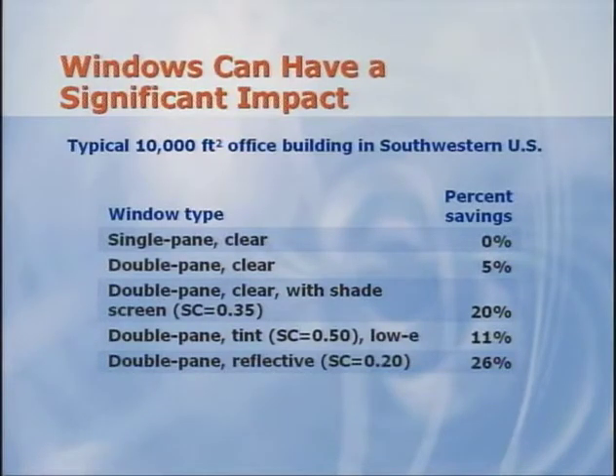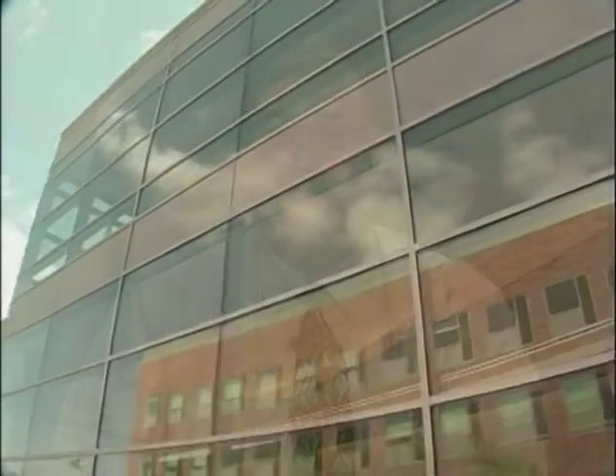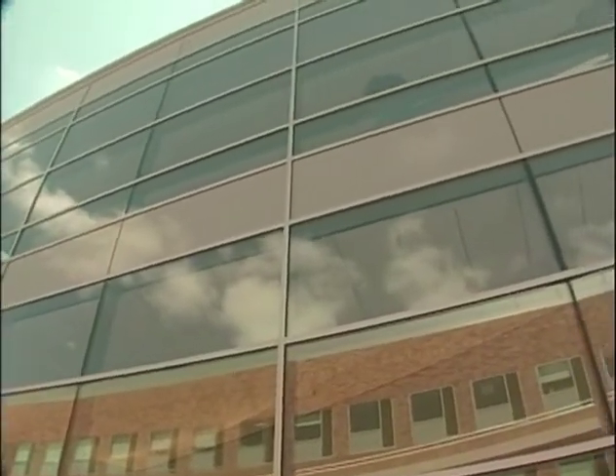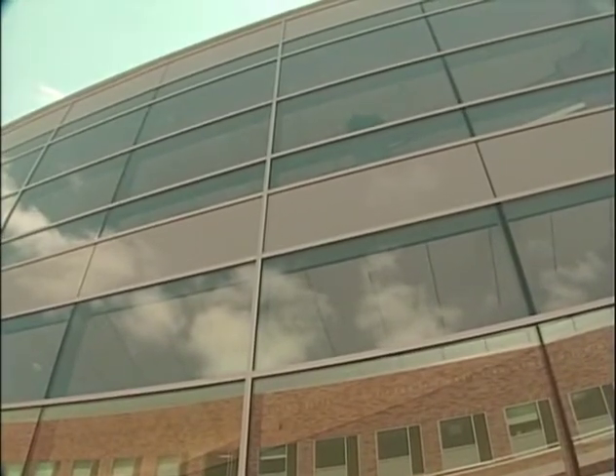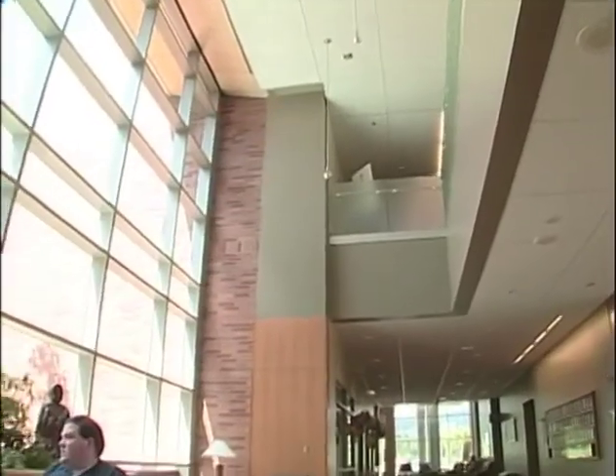A new building wouldn't see as much savings because of the minimum requirements in Energy Code and ASHRAE 90.1. In this case, of course, the savings from using higher performance glazing options is not as dramatic, but can still be significant. Changes to window glazing are easily modeled to see the impact on energy performance for a building. Work with the project's architect to define suitable options to model, and you can show the design team the effects of the energy performance from the choices made.